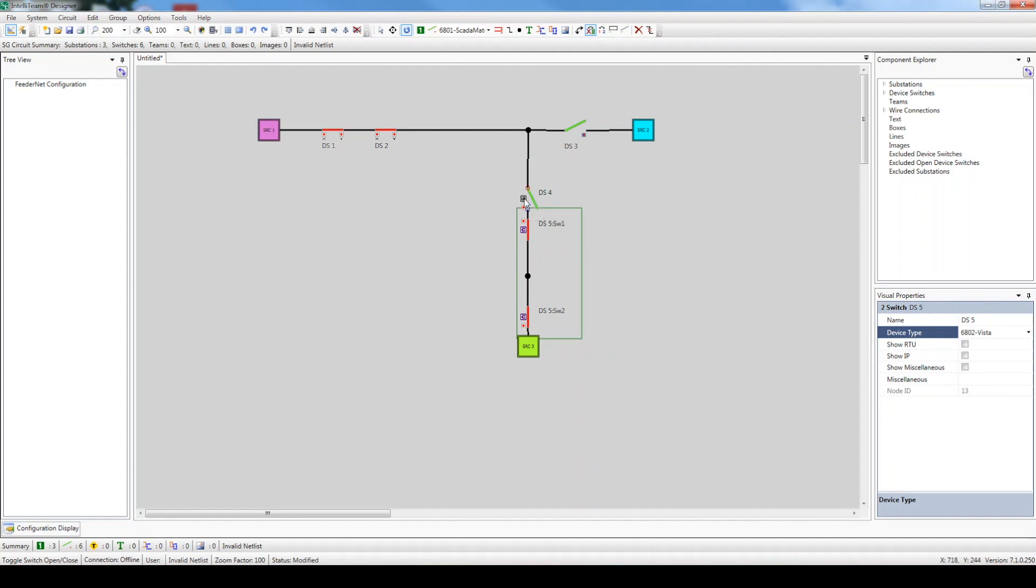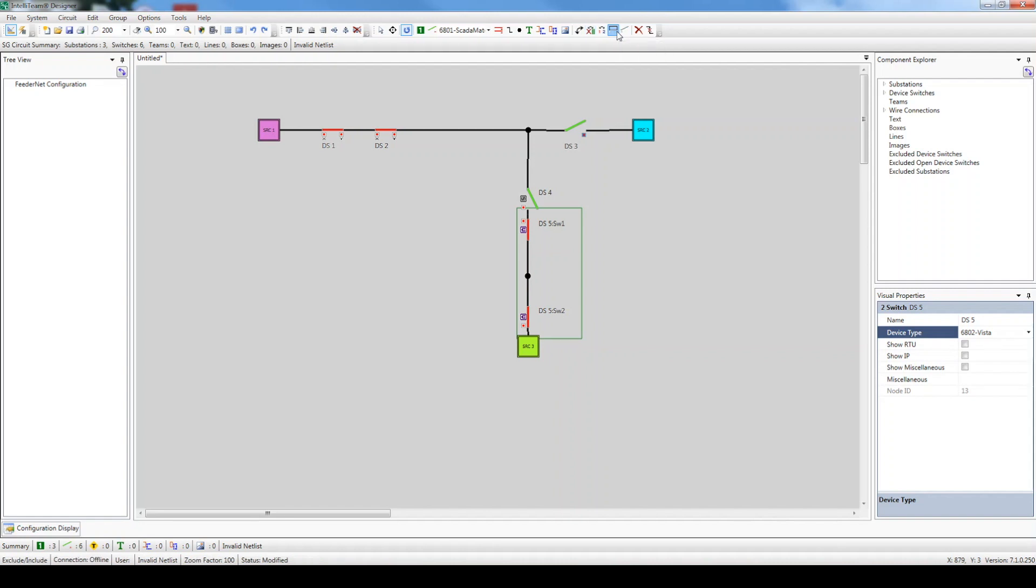There are also other draw functions within Designer. For example, if our Vista gear included manually operated switches, you can exclude them from the IntelliTeam system by either clicking the Exclude Include button for normally closed switches, or the Exclude Include Open button for normally open switches, and then selecting the switch. Notice that the switch becomes grayed out once excluded. Since our gear includes motor operators on both ways, we will insert it back into the circuit.